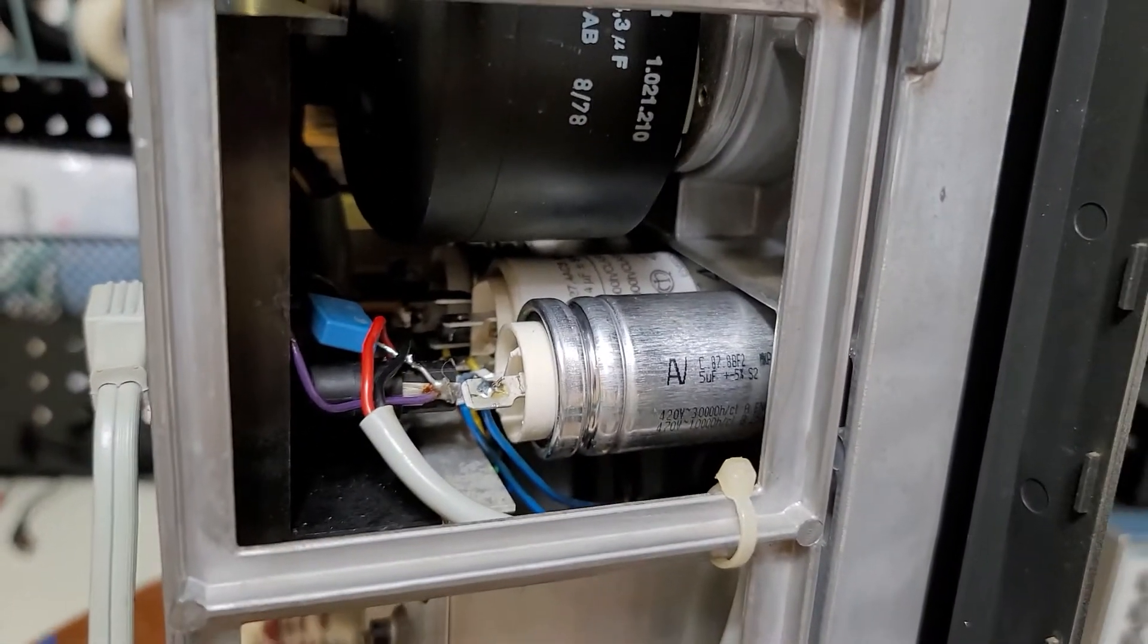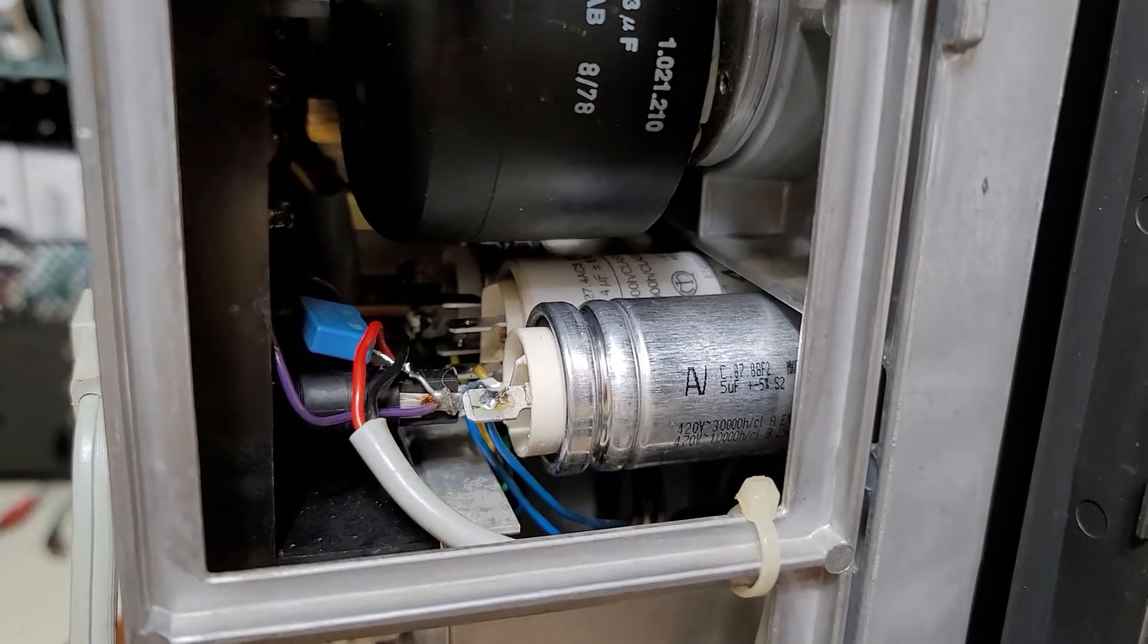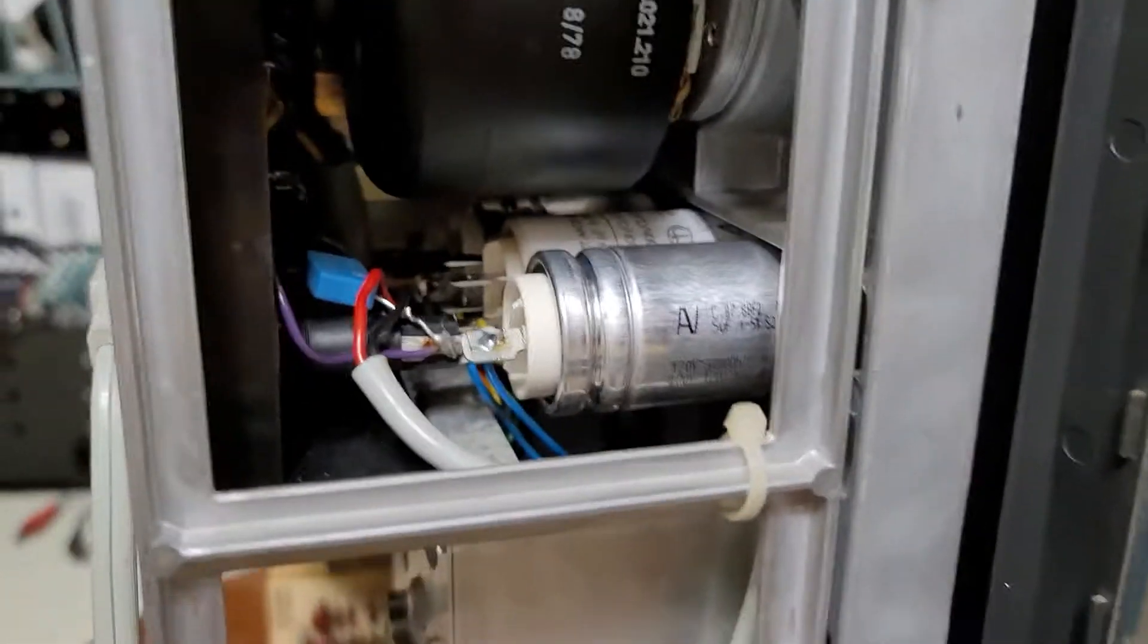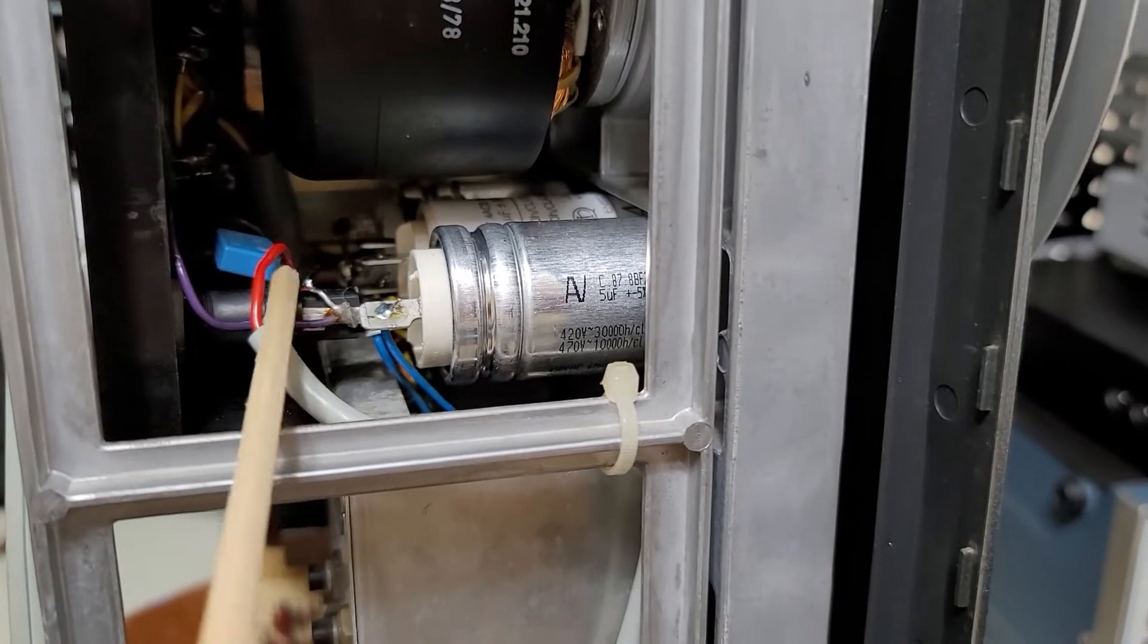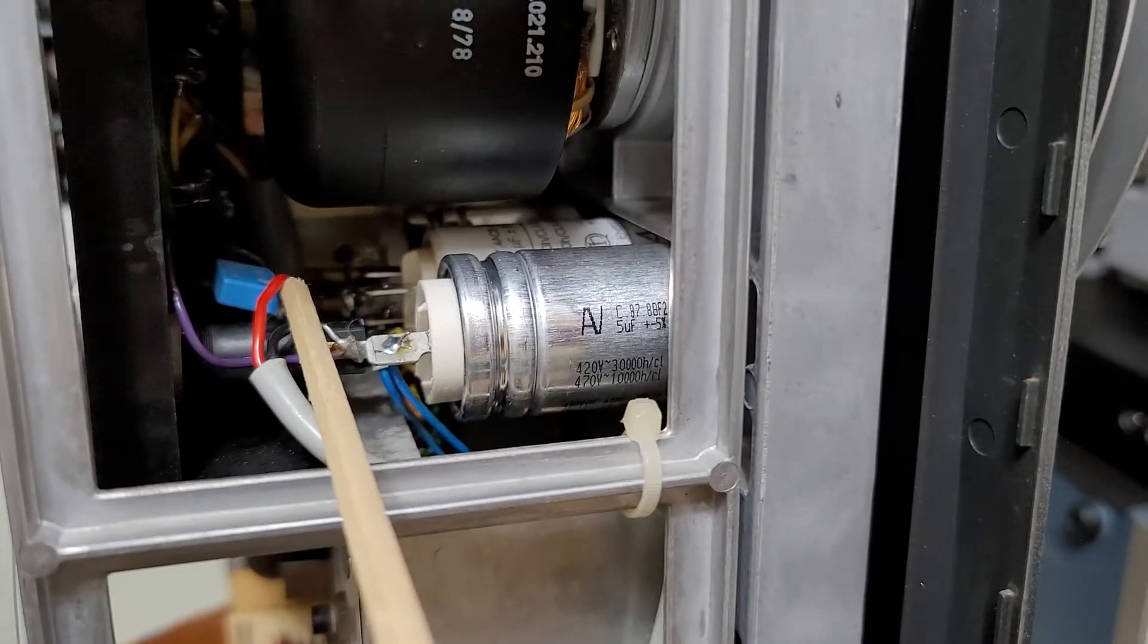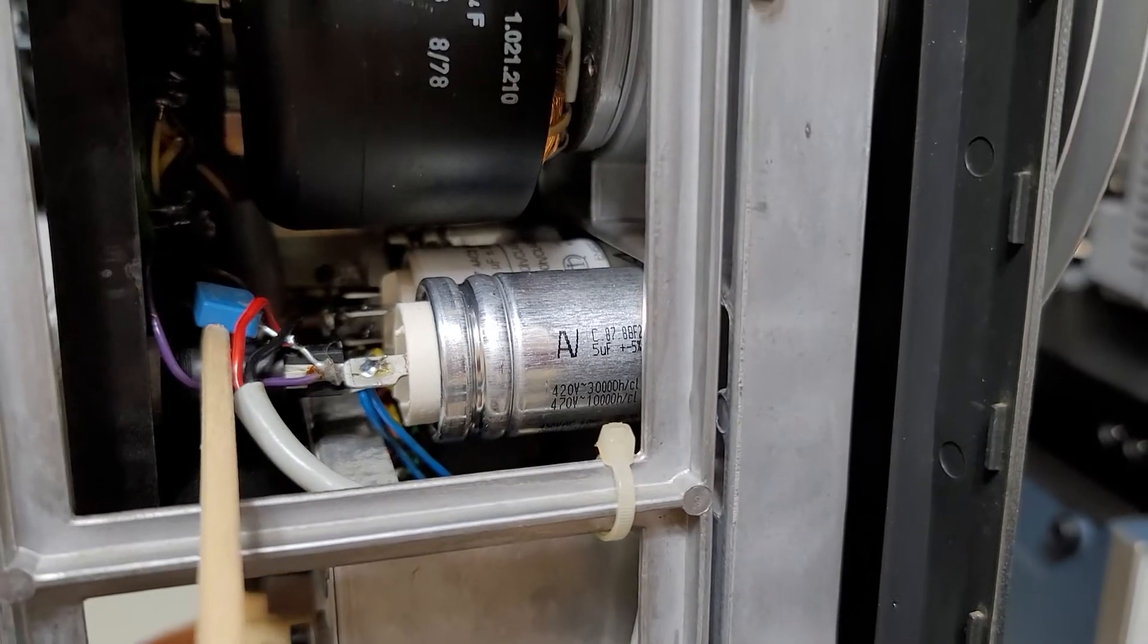The motor run capacitors, all brand new. These are notorious for leaking. And if you can see here, this is a safety cap - this thing was busted. The original was busted, changed it out brand new.